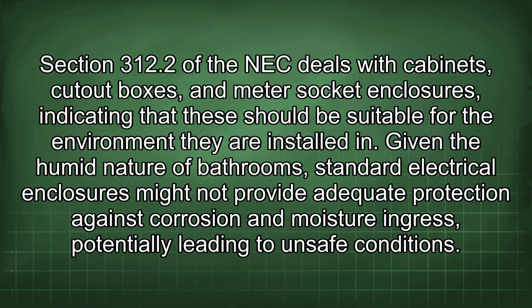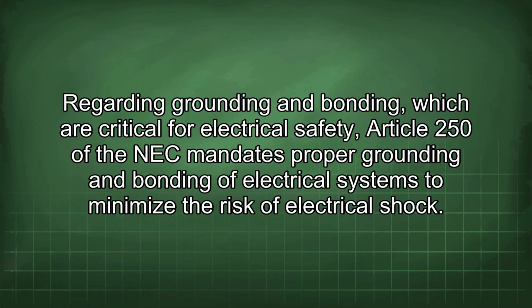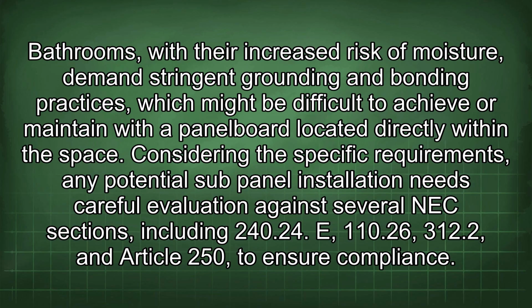Given the humid nature of bathrooms, standard electrical enclosures might not provide adequate protection against corrosion and moisture ingress, potentially leading to unsafe conditions. Regarding grounding and bonding, which are critical for electrical safety, Article 250 of the NEC mandates proper grounding and bonding of electrical systems to minimize the risk of electrical shock. Bathrooms, with their increased risk of moisture, demand stringent grounding and bonding practices, which might be difficult to achieve or maintain with a panelboard located directly within the space.